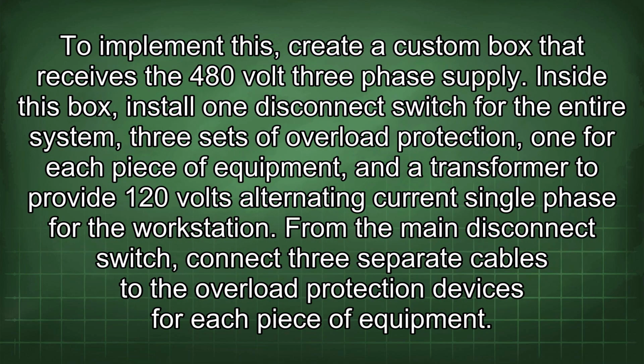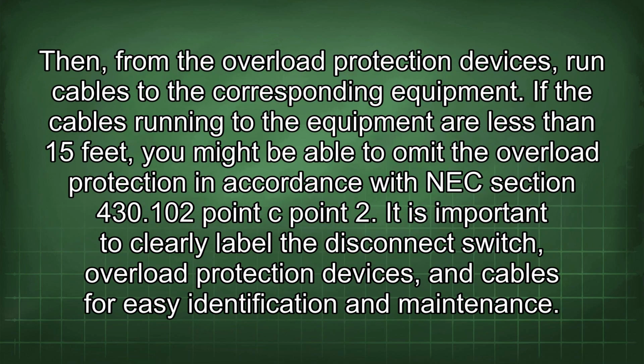To implement this, create a custom box that receives the 480 volt three-phase supply. Inside this box, install one disconnect switch for the entire system, 3 sets of overload protection, one for each piece of equipment, and a transformer to provide 120 volts alternating current single phase for the workstation. From the main disconnect switch, connect 3 separate cables to the overload protection devices for each piece of equipment. Then, from the overload protection devices, run cables to the corresponding equipment.